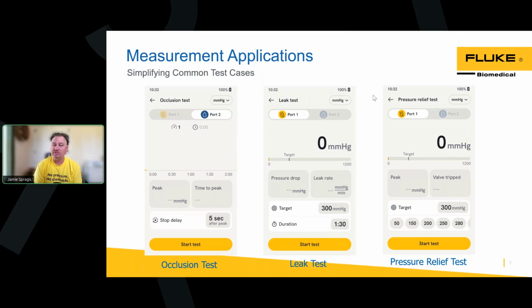But for the leak test, again, you would select your target, and then you would select your duration, how long you want to hold that leak test. And again, the DPM5 will calculate your pressure drop over time and the leak rate. So just a really, really crafty way to do leak testing. We were talking to some students at AMI, and they were doing a project where they were calculating a lot of these measurements by themselves. They were saying, oh man, this is a great instrument that we could have used to remove those calculations. So again, when you're doing the leak test, part of our engineering team is really, really proud of that.